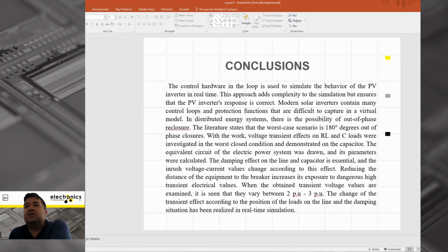In distributed energy systems, there is a possibility of out-of-phase reclosing. The literature states that the worst case scenario is 180 degrees out-of-phase reclosing. The voltage transient effect on the RL and C capacitor loads was investigated in the worst closing condition and demonstrated on the capacitor. The equivalent circuit of the electrical power system was drawn and its parameters were calculated. The damping effect on the line and capacitor is essential, and the inrush voltage and current values change according to this effect. Reducing the distance of the equipment to the breaker increases its exposure to dangerous high transient electrical values.